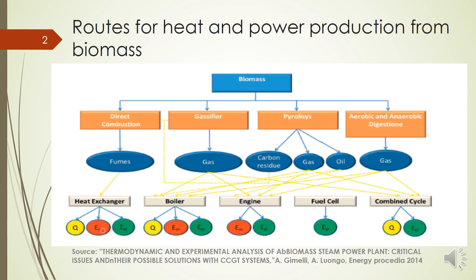That heat can be further used for power production through a proper cycle. Alternatively, we can gasify the biomass and that syngas or producer gas can be used in a boiler for heat and steam turbine, or we can run the producer gas in an IC engine coupled with a generator to get electrical output. We can also use the producer gas in a fuel cell, which will directly convert it into electricity. A combined cycle can also be used. Similarly, pyrolysis gives biochar which can be used as fuel in a boiler, or the oil and gas from pyrolysis can be used in these different modes.